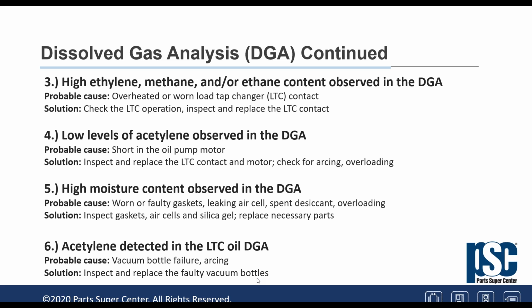The other item says low level acetylene. Acetylene is always a sign of arcing. In other words, unless there is arcing in the oil, there's no acetylene. What could this arcing be coming from? As it's written here, it could be a motor, or it could be the core. If there are multiple core grounds, there may be some arcing in the lamination that creates acetylene. In this case, the acetylene will be at a very, very low level, around 100 parts per million, and that depends upon how many gallons we have in the tank. But again, acetylene is always something to worry about because it's arcing.